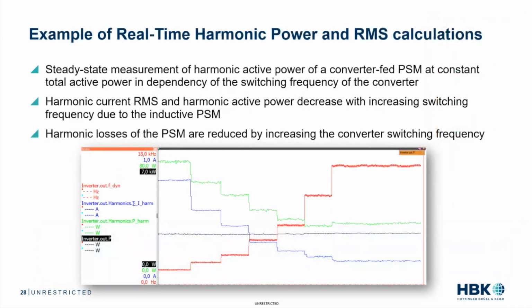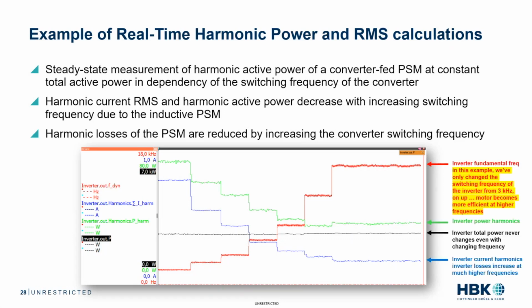Well, here's an example of a real-time harmonic power and RMS calculation. So in this example, we took a steady-state measurement of a harmonic active power of a converter-fed PSM at constant total active power, in dependency of the switching frequency of the converter. So basically, what we did is just change the switching frequency of the inverter. So you can see, starting from the left, it was about 3 kilohertz, and then we just increased it to 5 kilohertz, and so on and so forth.